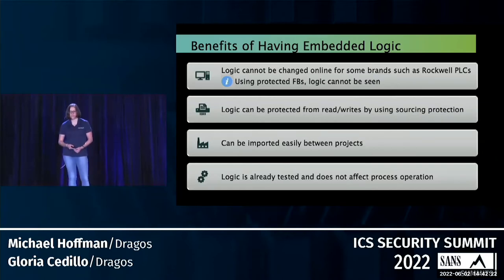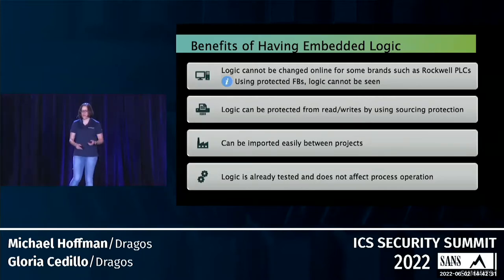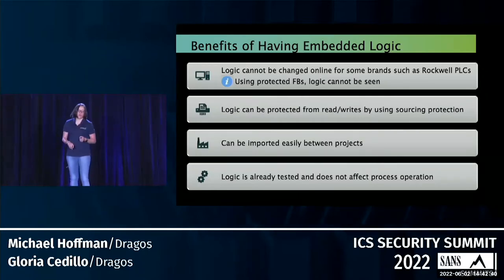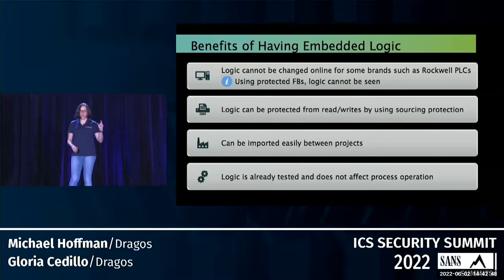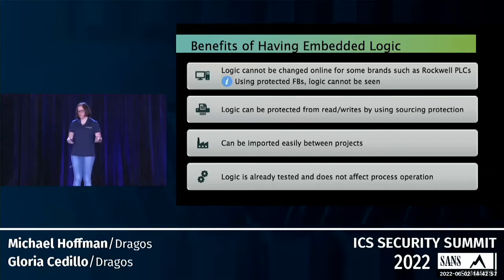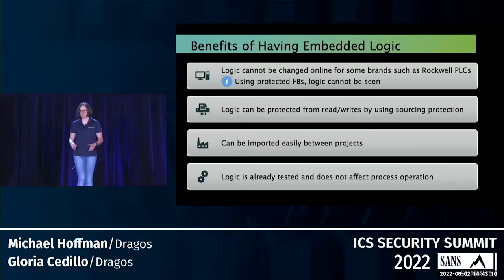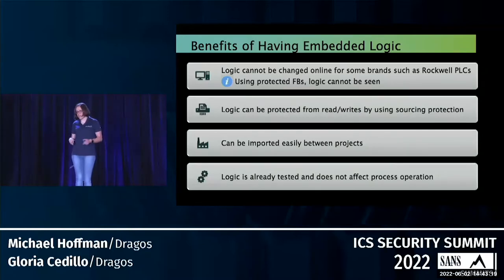The logic can be protected from read/writes. In Rockwell you can use sourcing protection — it's a file where you put the blocks you want to protect, then take that file off the computer. Nobody can get into those blocks because they don't have the file. Another advantage is those blocks can be imported easily between projects — just take the block you created, import it to another project, change the tag or use the same tag, and that's it. You don't have to recreate all the routines. You just create an AOI or a library, and the logic has already been tested — it's not something you're creating and testing on site.